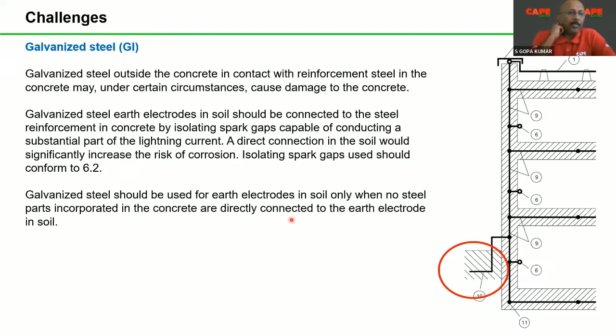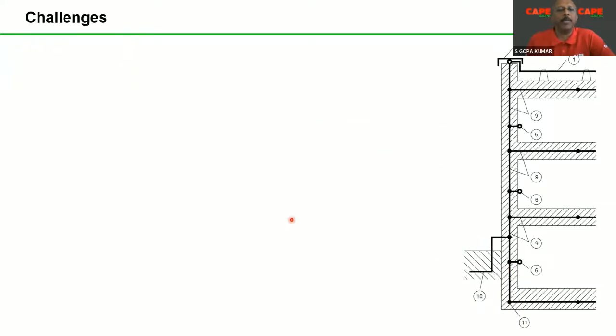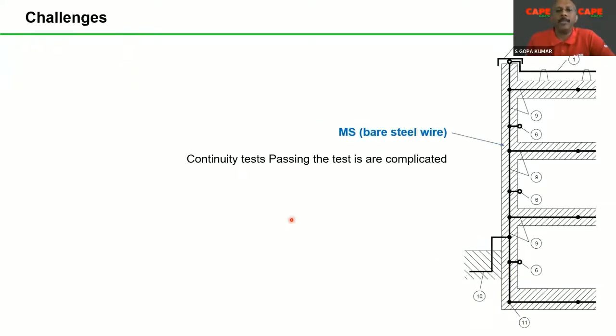Why I am very specific in this particular case is whenever we design, always people try to mention that use GI because GI is cheap. Use MS because MS is cheap. So GI, these are the challenges. Other case, people always try to use, instead of, the first recommendation is you use your MS conductor, the rebar itself. The standard says to use an additional conductor with a smooth surface. The second recommendation from the client is then you use a bare conductor. That means you use a steel conductor, round, smooth surface, but without any coating.